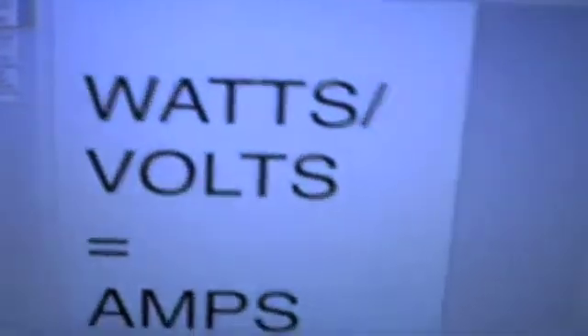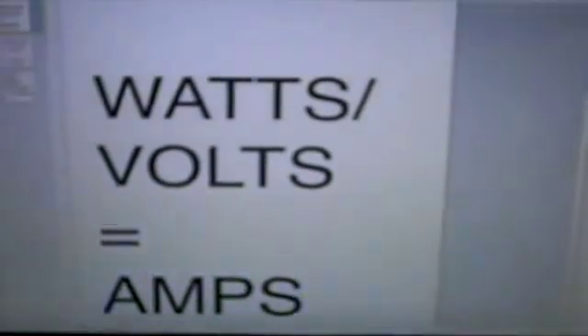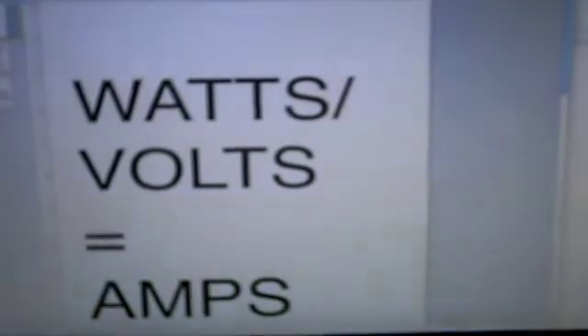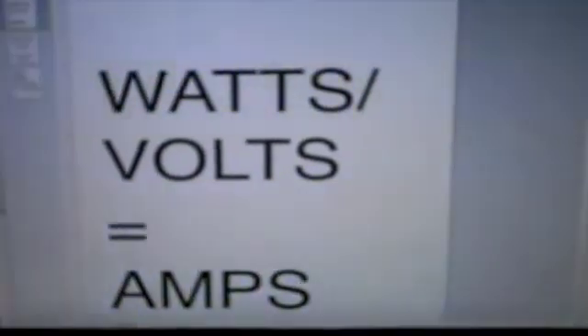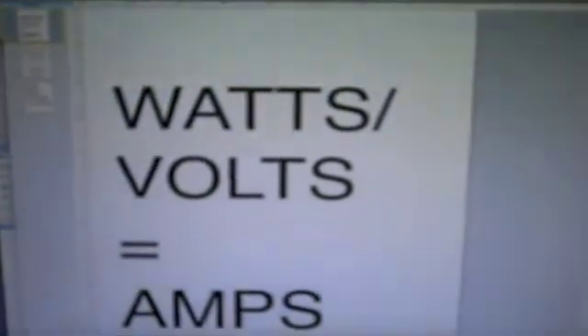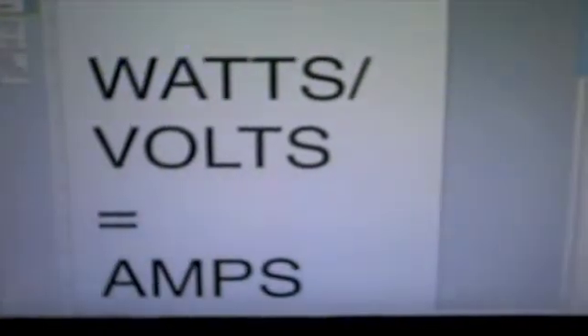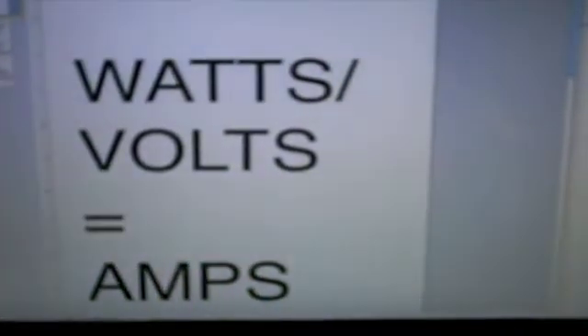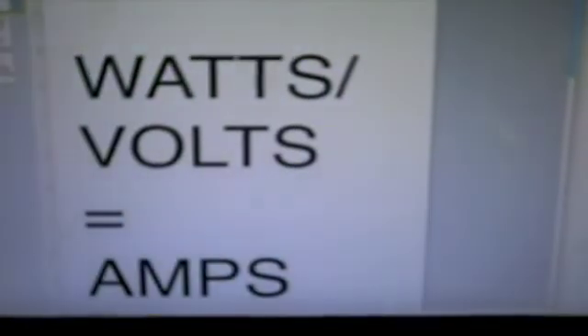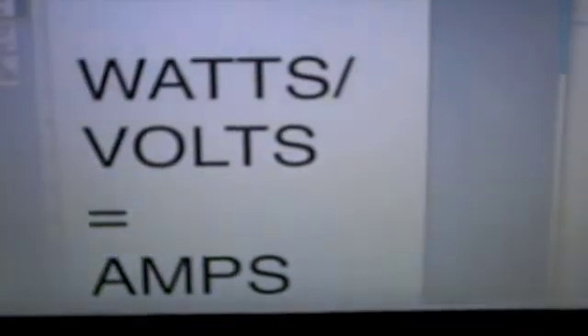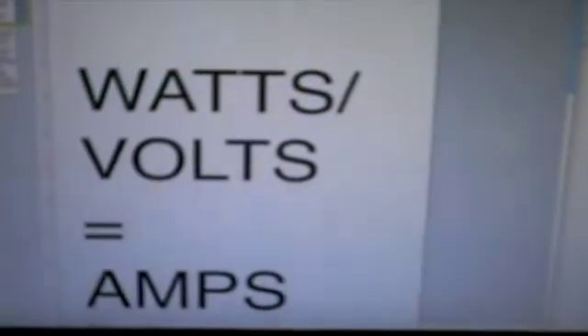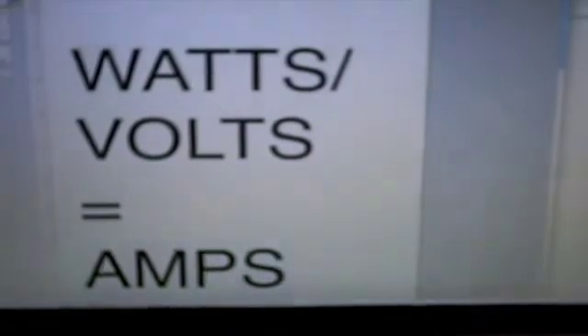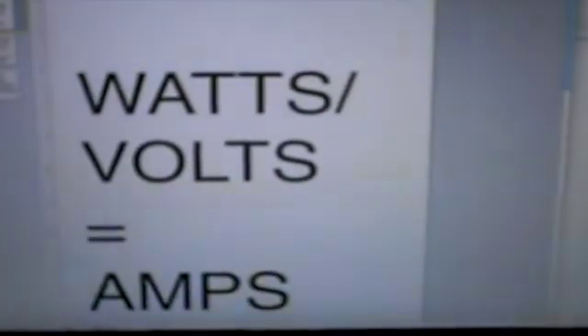Let's talk about power for just a little minute here. What we're worried about is current, amp levels. When you blow a circuit breaker, what that means is you've drawn too much current or too many amps over that circuit. They're set up at different levels depending on the size of wire behind it, to make sure the wire doesn't burn up. The rating on the circuit breaker is in amps, and the way you figure the number of amps you're using on any piece of equipment is to take the watts (which we think of often as a volume thing) divided by volts equals amps.